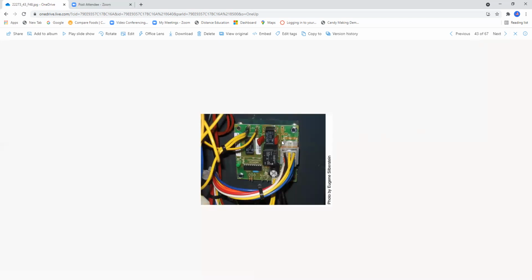And you do have a provision. They usually have pins right here. I believe these are your shorting pins in order to energize the defrost with an engineering bypass wire. We don't call that a jumper, by the way, in order to bypass the electronic timer to test the defrost action of this thing.